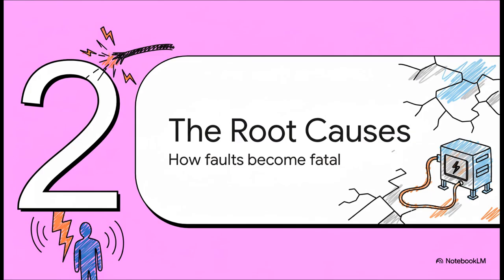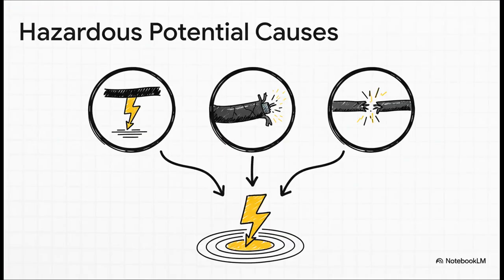Okay, so we've got the what down. We know what touch and step potential are, but why do they happen? What has to go wrong for a perfectly normal piece of gear to suddenly become so dangerous? It usually comes down to a few common culprits. You could have a direct phase-to-earth fault, where a live wire literally touches the ground or something connected to it. Or the insulation on the wires could get old, crack, and fail over time. And then there's a really sneaky one: a problem with the protective wiring itself, like a broken neutral wire. Any of these can kick off that earth potential rise and create a really dangerous situation.